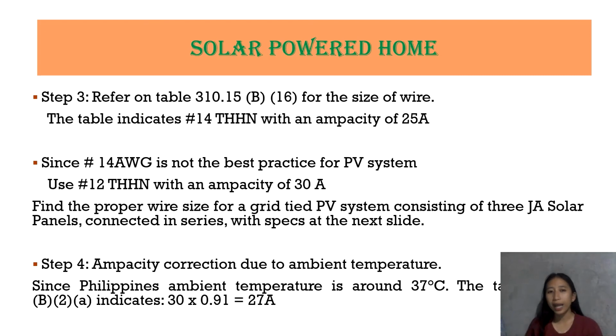Okay, so after that, we are going to move forward to step 3, kung saan we are going to refer or titingnan natin yung table 310.15 B16 para malaman natin yung mga sizes ng wire. So, the table indicates that number 14 THHN with an ampacity of 25 amperes, yun lang daw ang gagamitin natin. Okay, so since number 14 AWG is not the best practice for PV system, we are going to use the number 12 THHN with an ampacity of 30 amperes.